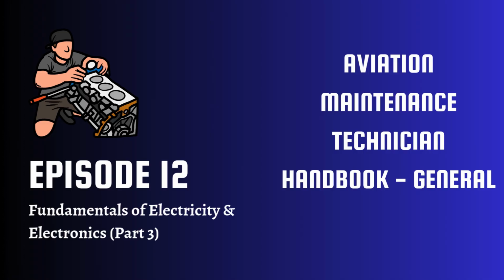Got it. Maintenance points, commutators again. What should AMTs absolutely not use? Never, ever use emery cloth or steel wool on a commutator or brushes. Emery contains conductive, abrasive particles that embed in the soft copper and the insulating mica. This creates shorts and continuous sparking. What should be used? Only approved commutator cleaning stones or very fine sandpaper designed for electrical work, and always clean away all dust thoroughly.